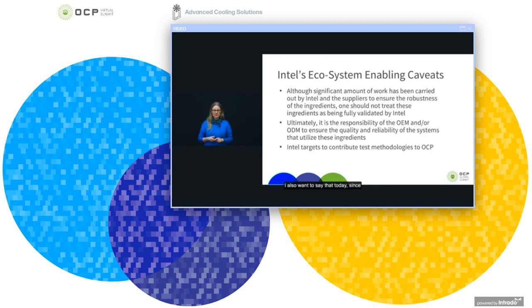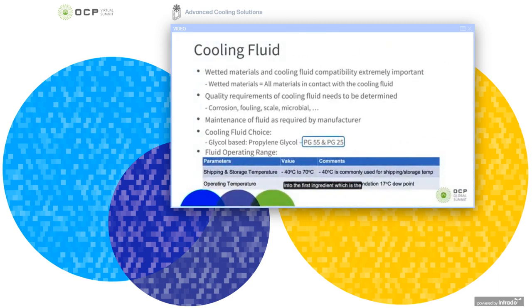And with that, I also want to say that today, since there are no standard methodologies really within the liquid cooling community of how to test this, Intel also targets to contribute to test methodologies to OCP. So if we're jumping into the first ingredient, which is the cooling fluid, we're talking about really here the wetted materials. So those are all the materials that are in direct contact with the cooling liquid. And we really need to ensure that there's compatibility between the cooling liquid and all the wetted materials that are being used. This is extremely important.